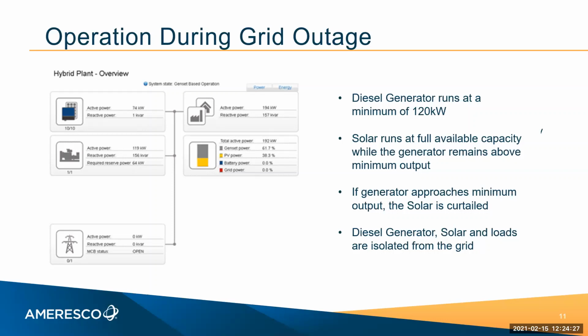The load of the building was 194 kW, 119 kW is being fed from the generator, and 74 is being fed from the solar. So 62% of the power was being fed by the generator, and the remaining 38% was coming from the PV. If the load increased and the available solar was higher than, say, 74, that would creep up with the load as long as the generator was above that 120 kW minimum set point.